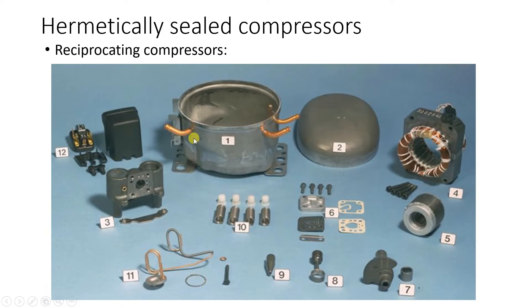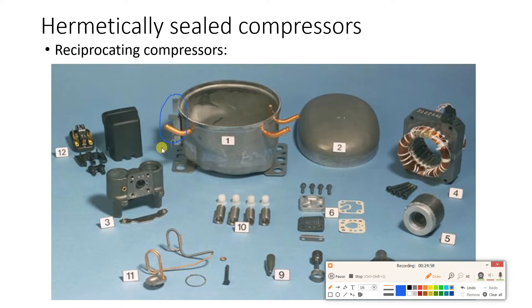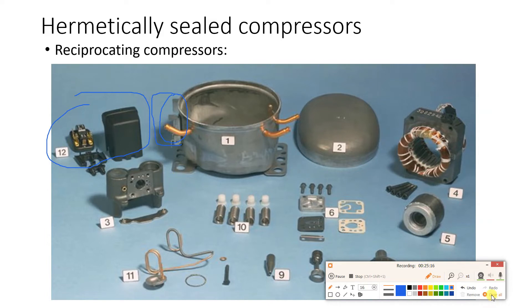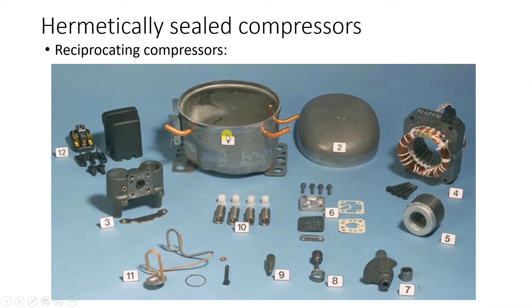The components of the hermetically sealed compressor numbered are: the outer shell (welded), three copper tubes (suction, discharge, charging), electrical terminals, the cylinder, motor stator coil, rotor, cylinder head with gasket, crankshaft, connecting rod and piston, oil pickup tube, four springs (for vibration isolation), and internal discharge tube. Externally on the shell there are usually a relay and overload protector.